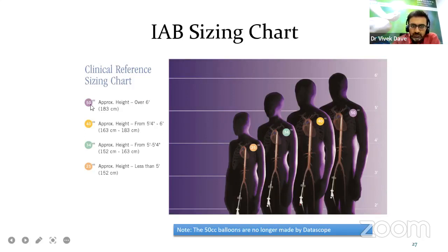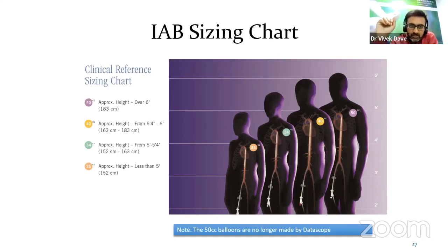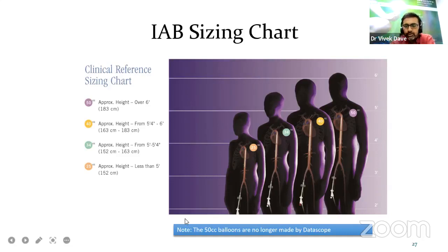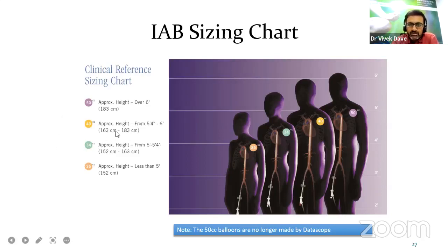If the height is over six feet, the 50 cc size balloon is used. Five foot four to six feet is 40 cc; five to 5.4 feet is 34 cc; and less than five feet is 25 cc. The 50 cc balloons are no longer made by Datascope, so the widely used sizes are 34 cc and 40 cc. The approximate lengths are 163 to 183 cm and 152 to 163 cm.